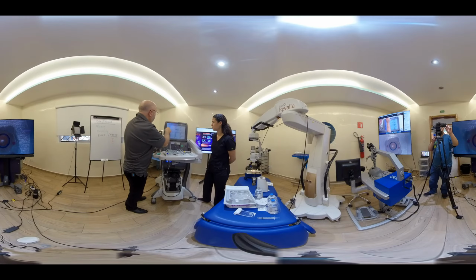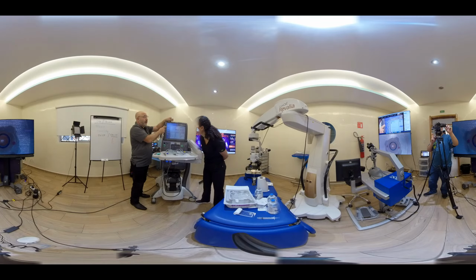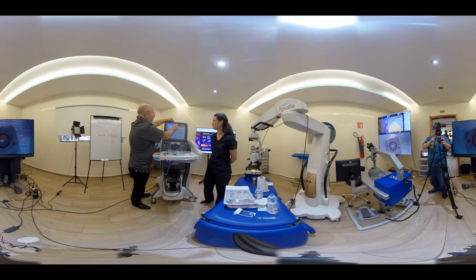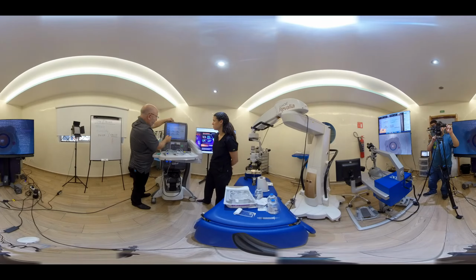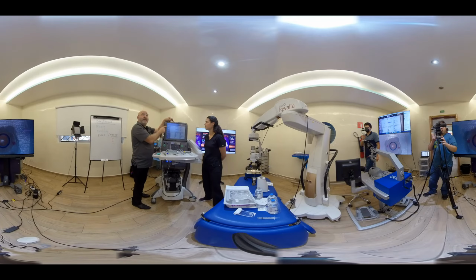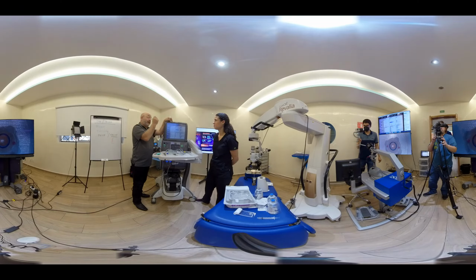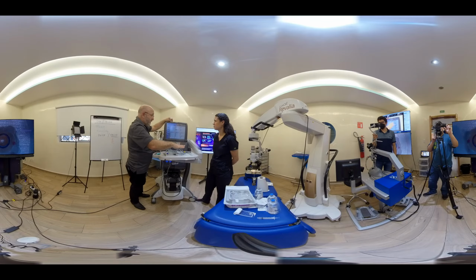So let's hit... Oh! Now, I've just set up Dr. Alcon here. What do we notice here under infusion? Are we set up for infusion or IOP? Infusion. Because there's no second button, I need to tell it in my doctor profile to turn on IOP, to enable that function. So we're going to come to IOP and enable. So now I'm going to hit save, and now the IOP button is turned on. It is activated, but it's not calibrated yet, so it's not orange and not filled in, it's grey. But after a successful prime, it should be okay. So let's hit the start prime.